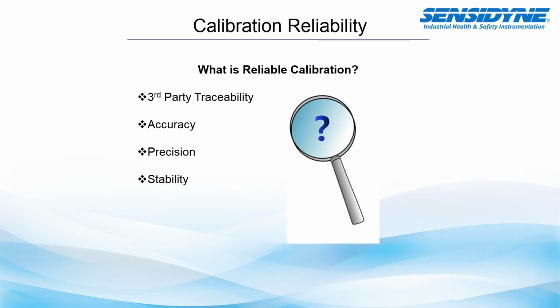So when we think of reliable calibration, there are four aspects that should be considered. The first is third-party traceability. The second is the accuracy of our calibration. The third is the precision of the calibration. And the fourth should be the stability of the calibration in line with the airflow source that is being calibrated.